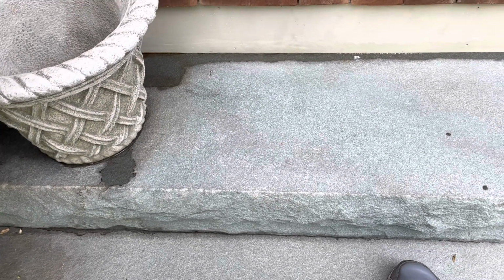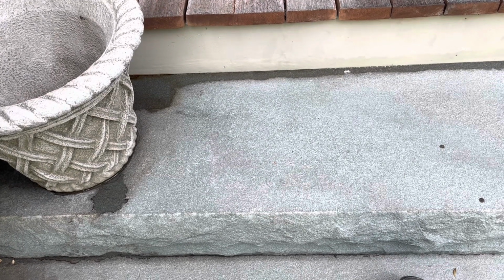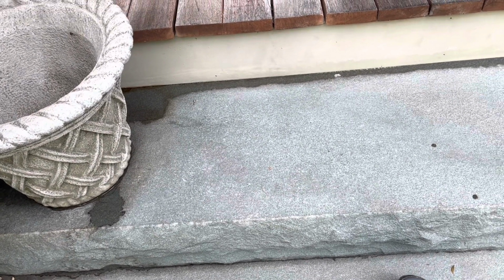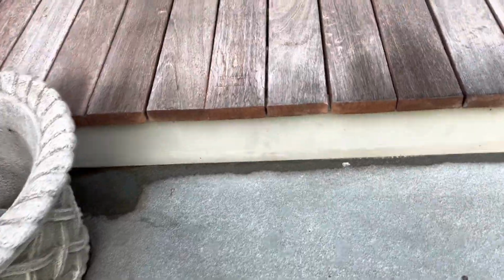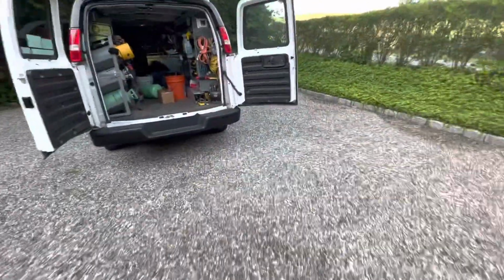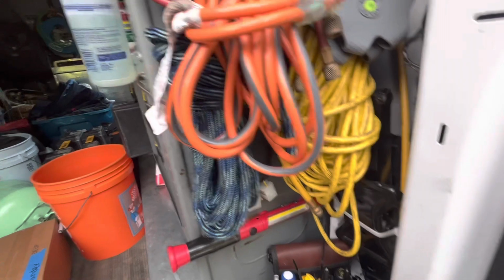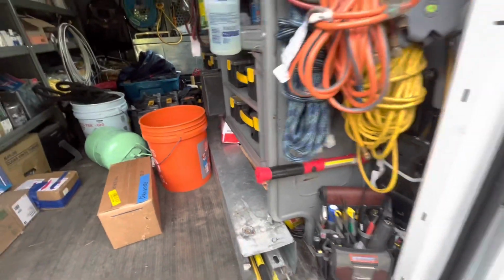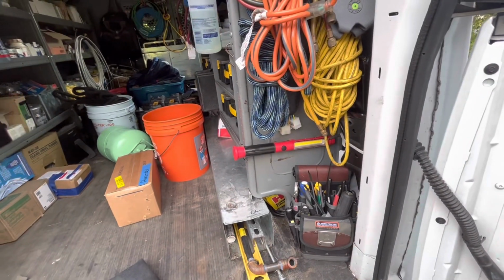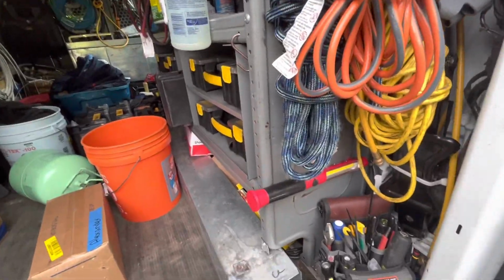May I come in just to check the inside of the main level? Sure. I just want to make sure the airflow is okay, and then I'll be outside doing everything else. So this is a simple, well, I don't want to say simple, it's a no cooling call. I have airflow inside. The filter check's good. Now we're going to go out and check the condenser. So let me grab my gauges.